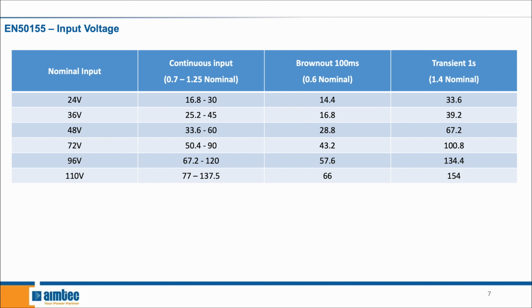So looking at the first row, where we have 24 volts nominal input, the continuous input needs to be between 16.8 and 30 volts. The brownout needs to be 0.6 times the nominal input voltage, so taking 24 volts and multiplying by 0.6 gives us 14.4. And the transient is 1.4 times the nominal voltage, which for our 24 volt example gives us a transient of 33.6.